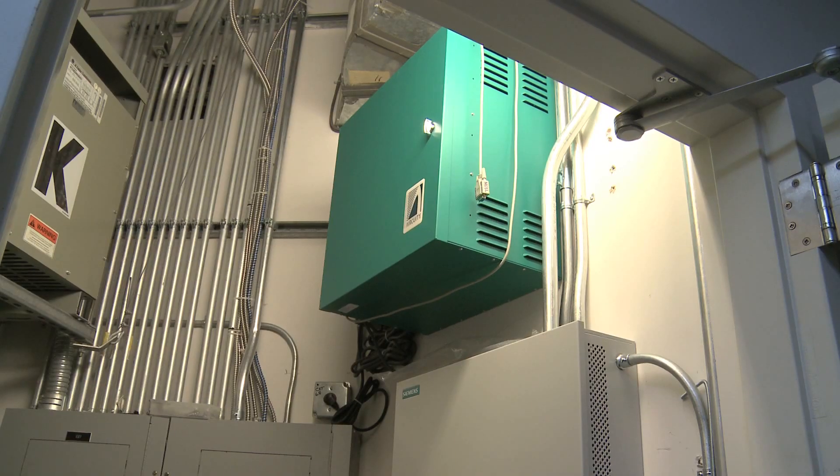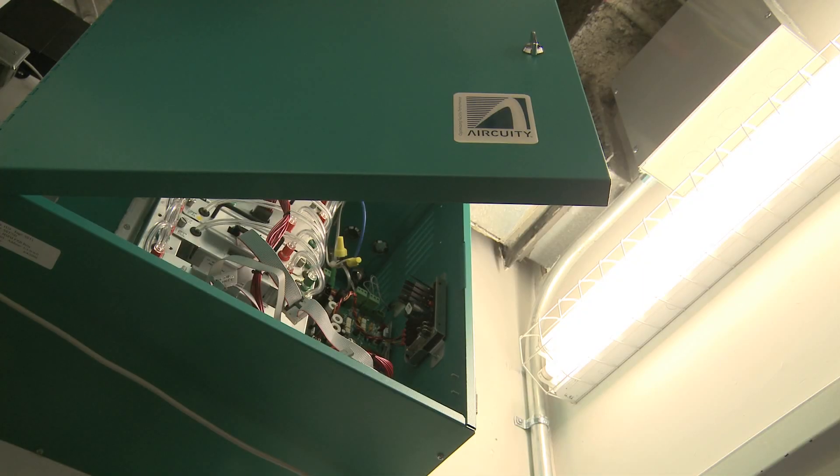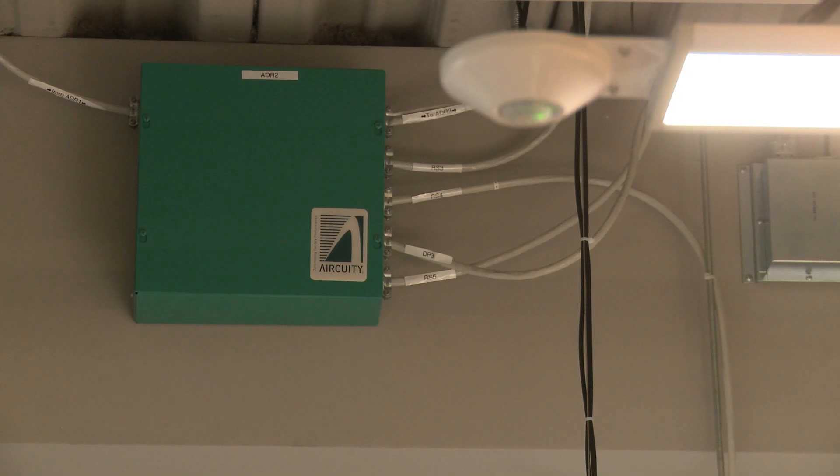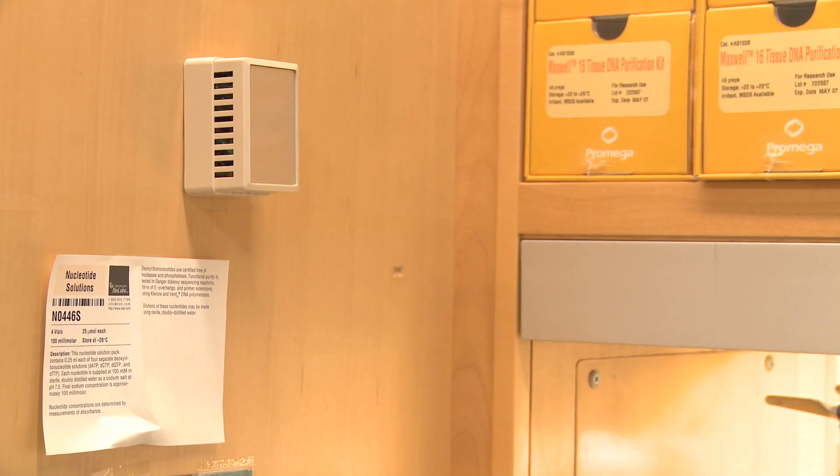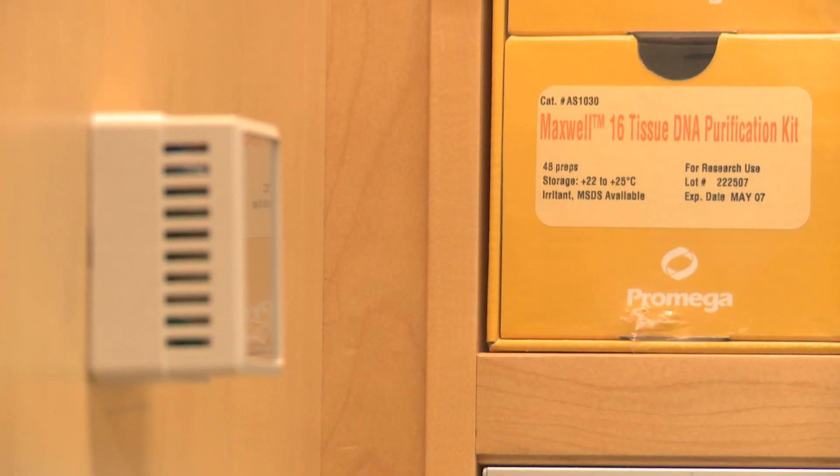The Aircuity system is a demand controlled ventilation system where you're pulling columns of air back to a series of sensors that monitor and measure the indoor environmental quality, then operate the variable air volume boxes that adjust the airflow to the lab based off of those readings or the real-time demand in the space.